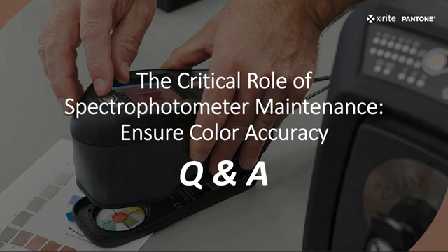So yeah, the canned air and the Q-tips are things that are identified specifically in the cleaning instructions for a variety of instruments. They also, by the way, tell you how to clean the calibration media. Obviously, if you calibrate on a dirty cal plaque, that misaligns things as well. So keeping all of that clean is really important.